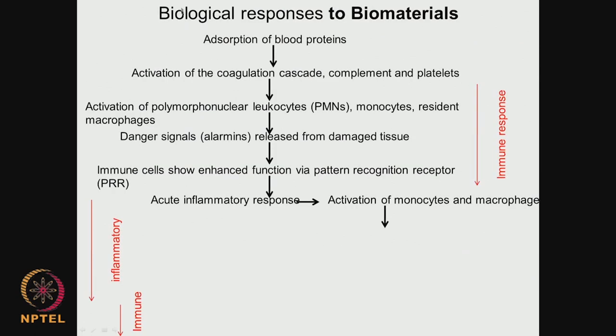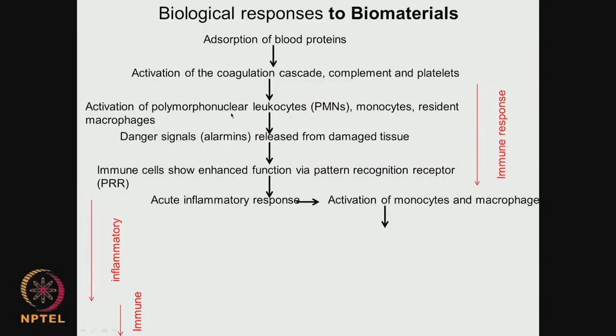Looking at the biological responses in more detail: adsorption of blood proteins is happening. If it is a blood-contacting device, then we have activation of the coagulation cascade — a fantastic cascade where many coagulation factors, one after another, keep happening, and finally you have coagulation. Then you are activating the complement — these are a set of proteins which get activated as the host defense mechanism. Activation of platelets then occurs. Then we have activation of polymorphonuclear leukocytes, monocytes, and then macrophages — certain cells which try to form the encapsulation of the biomaterial.